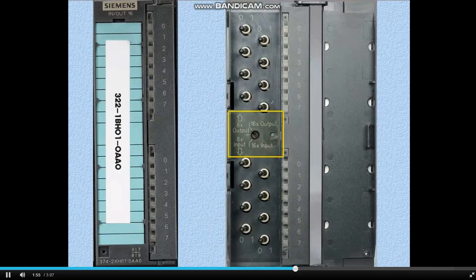In the center of the module is a slotted switch. When the switch is turned down, the module will function as a 16-input module, and all 16 switches will work. When the switch is turned to the center position, the module will function as 8 input and 8 output. The bottom 8 bits will be switches, and the top 8 bits will be LEDs. When the switch is turned to the uppermost position, as pictured here, the module will function as 16 outputs, and only the LEDs will work.